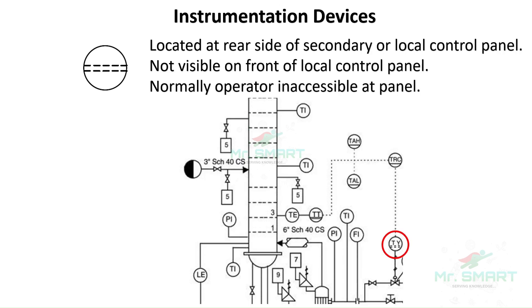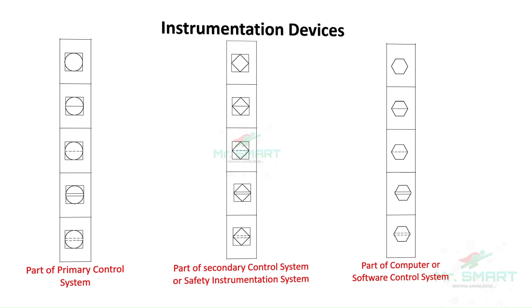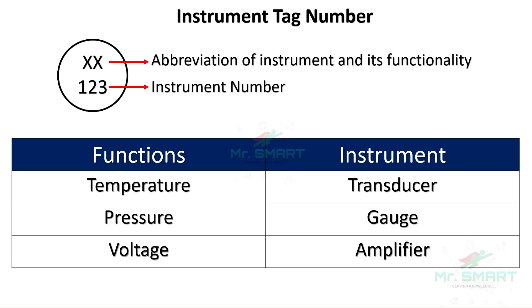Instruments mentioned inside a circle with double horizontal dashed line represent that the device is located at the back side of the secondary or local control panel, not visible at the front side, and cannot be accessed by the operator normally. Symbols enclosed within a square box represent they are part of the primary control system. Symbols in a diagonal square within a square box represent they are part of the secondary control system or safety instrumentation system. Symbols in a hexagon represent they are part of a computer or software control system. Instrumentation representation will have an instrumentation tag and an instrumentation number.